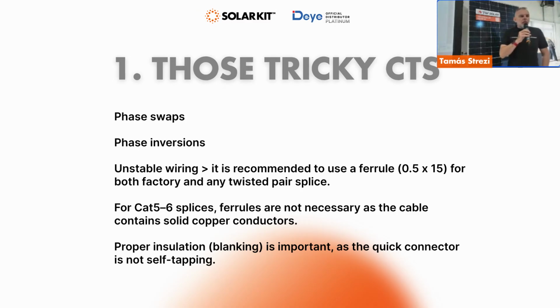One interesting issue during these extensions with Cat 6e was that the copper wire wasn't exposed properly. They assumed that the connecting terminals are self-cutting, which they are not. So you always have to make sure that the wires are properly stripped. I would also suggest using ferrules even on the factory connections, because the wires are really, really thin and they can be brittle when you insert them into the connection.